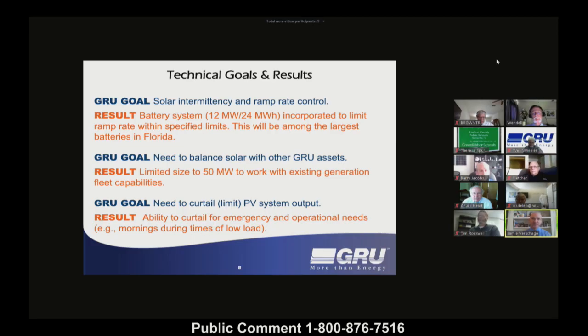In the ITN, GRU set a limit of 3 megawatts per minute up or down on the system's output. Origis is achieving this by incorporating a large battery capable of instantaneously discharging 12 megawatts and storing 24 megawatt hours of energy. This will smooth the system's electrical output and give time for GRU's rotating units to ramp up and down along with it. This battery will also be among the largest in Florida.